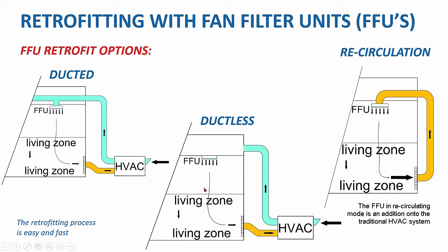The second option is a ductless option. There we see that the duct from the HVAC unit is going to the supply plenum, and from the supply plenum air is going to the fan filter unit and to the living zone. The last option is an interesting one. There we see recirculating of air. Here we can increase the amount of air changes in the room. What's actually happening is that the air from the room, the contaminated air, is going through a low return and going back to the fan filter unit and is filtered. So the air is circulating a couple of times through the fan filter unit and cleaning the air from the room.